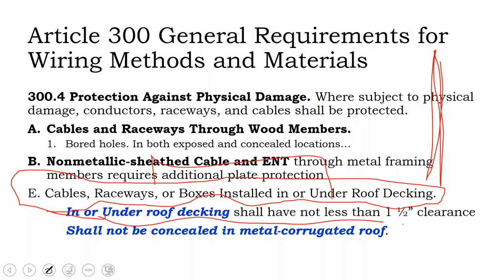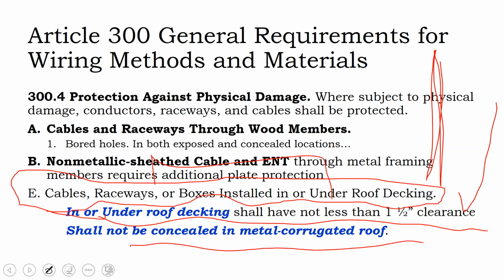If you're going underneath the roof decking, you need to have at least 1.5 inches of clearance underneath the roof decking. So hopefully these roofers are smart enough not to be using 4-inch nails when only a 1-inch nail is needed, that they're not going to just be putting metal dangerous spikes into the underside of your rooftop. But you have to have a 1.5-inch clearance underneath the roof deck, and you also cannot conceal the wires in your metal corrugation. So sometimes in your metal corrugation, you get a rolled form that looks like that, and you might think, oh, can I shove a conduit underneath here and conceal the wires? You're not allowed to conceal wires in a metal corrugated rooftop.